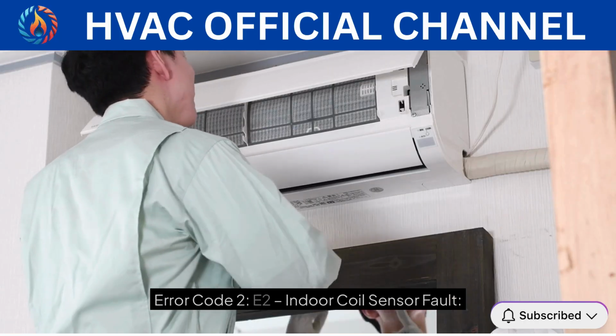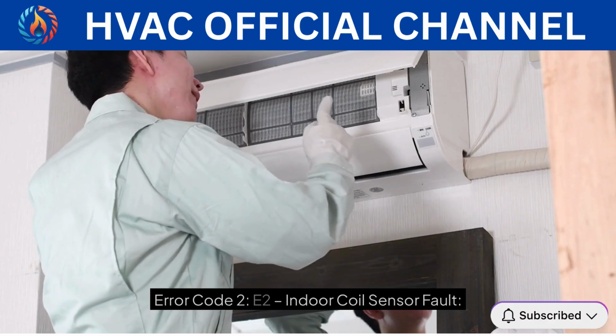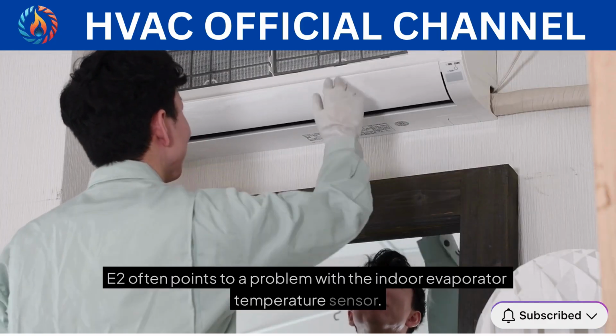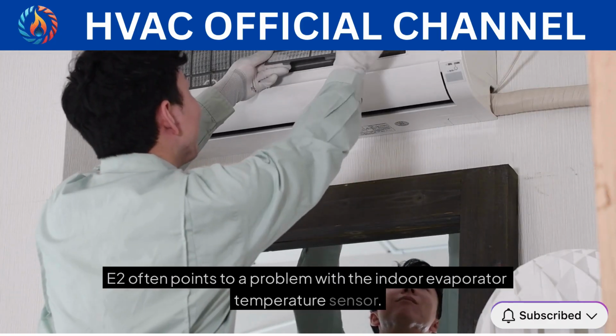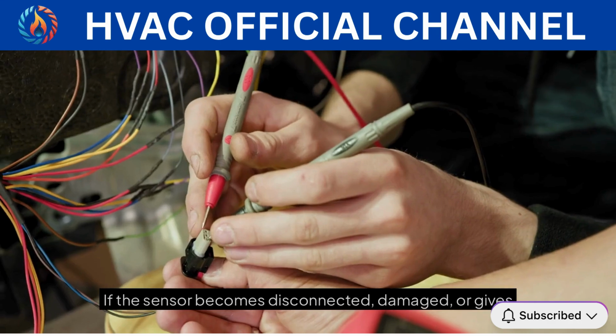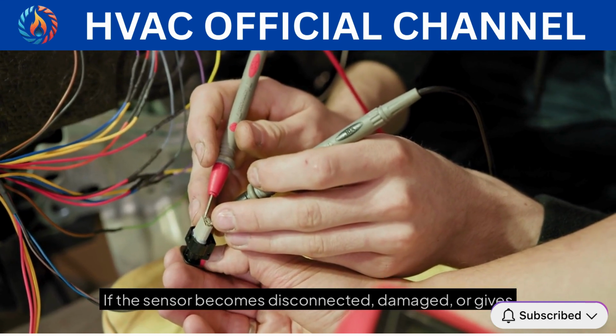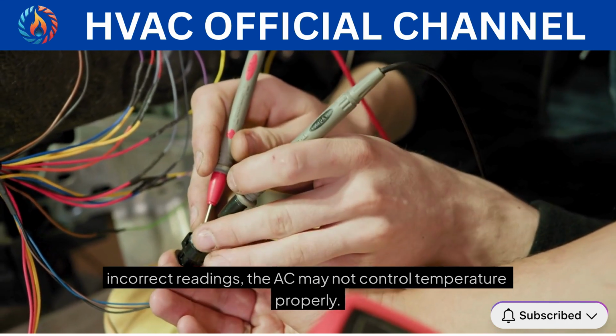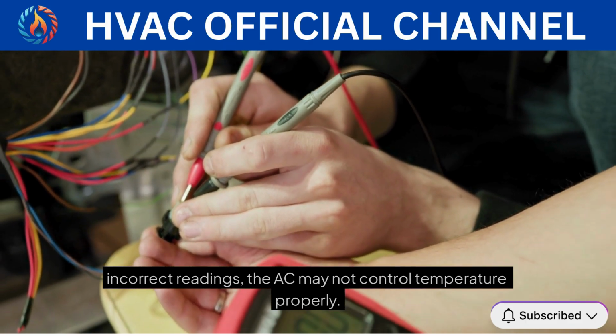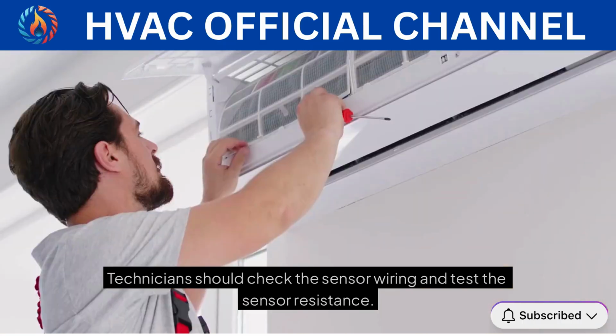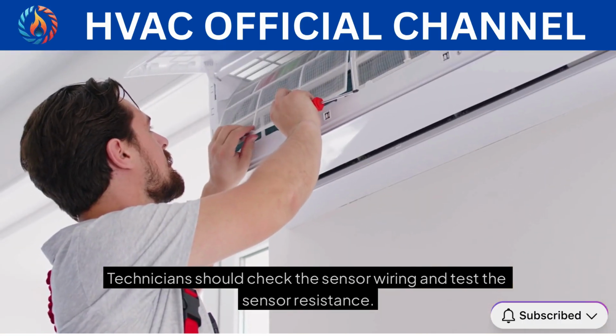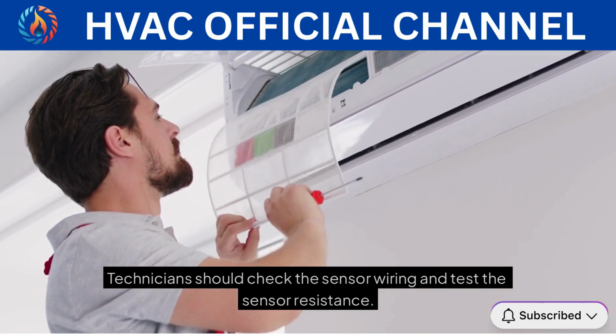Error code 2, E2, indoor coil sensor fault. E2 often points to a problem with the indoor evaporator temperature sensor. If the sensor becomes disconnected, damaged, or gives incorrect readings, the AC may not control temperature properly. Technicians should check the sensor wiring and test the sensor resistance.